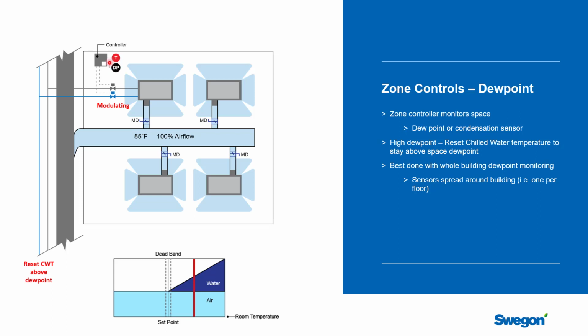Now, to do that, you really need a dew point sensor as opposed to a condensate sensor. If you have a condensate sensor, you already have a condensation problem by the time that sensor's tripped. A dew point sensor will warn you that you're heading in the wrong direction, that you're getting close to a condensation situation. That's why dew point sensors are considered a superior solution. So resetting the chilled water to stay above dew point is a legitimate control sequence to help manage a possible condensation situation. And normally we'd say try to stay 1 degree Fahrenheit above the dew point of the worst zone in the building.